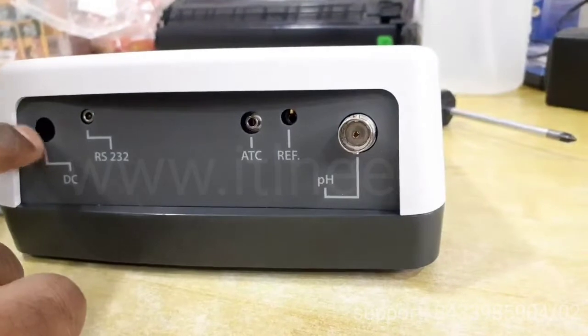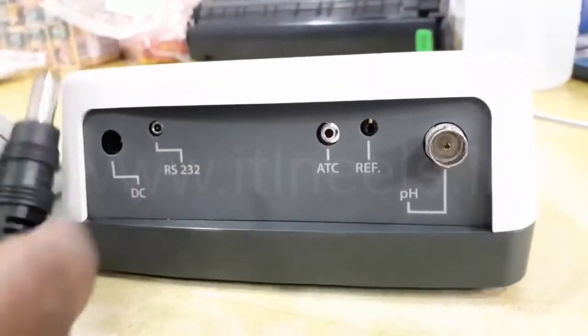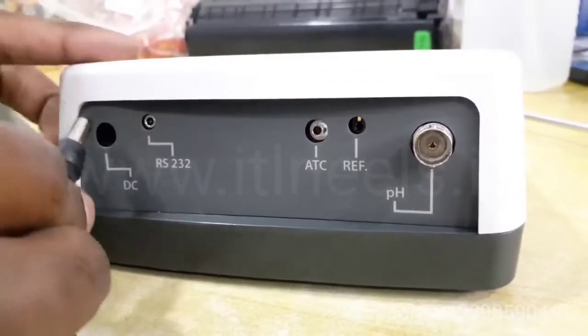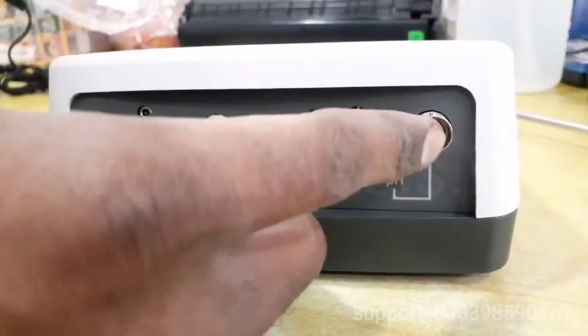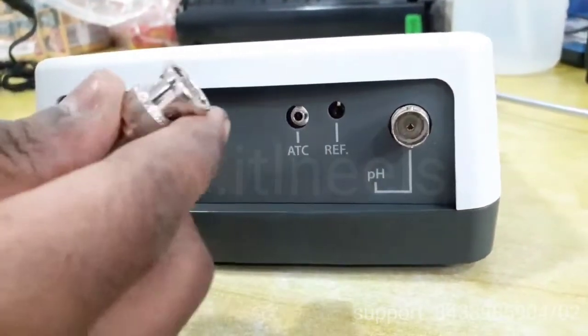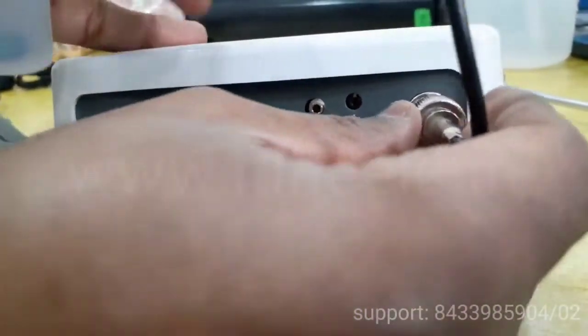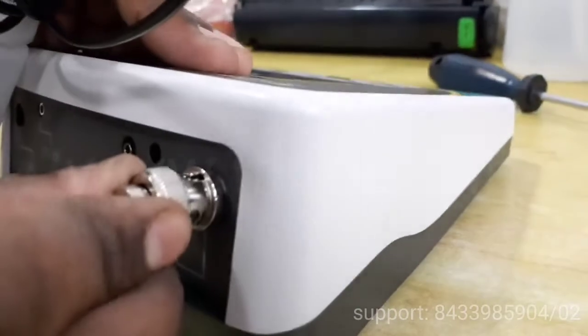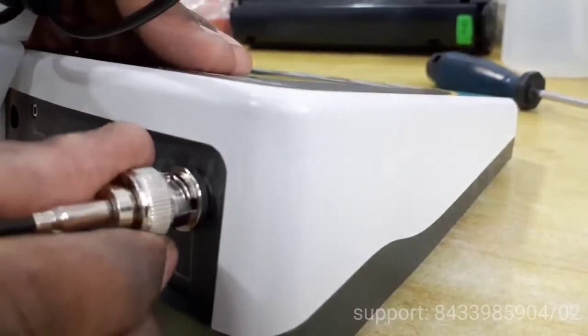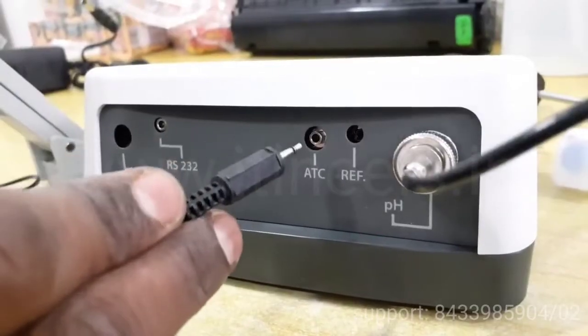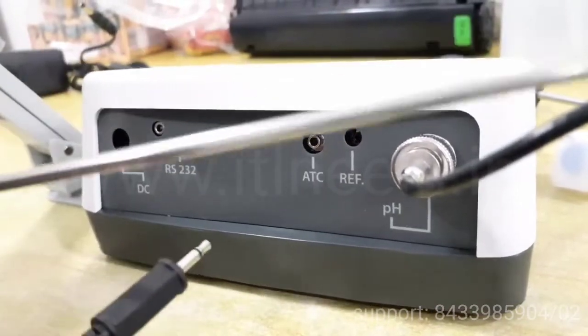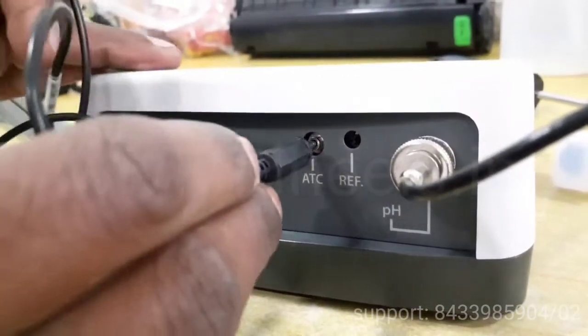Now this is the back section of the meter. This is where you connect the power supply DC. This is the BNC connection for connecting the BNC of the pH electrode. You have to push it over here first, then twist it. This is for connecting the ATC probe. This is the ATC probe.